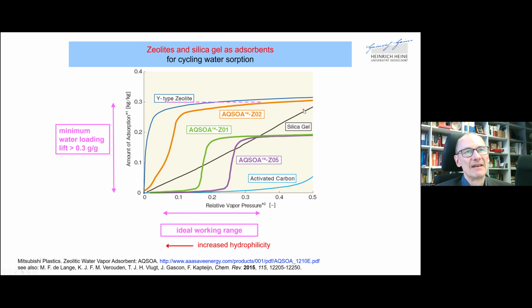So silica gel, because it's amorphous and has a quite large distribution of pores and pore sizes, will take up water over the whole range of water vapor pressure. And that is not really attractive, because if one works in this range here, there's only a small uptake over this range and not an S-shaped curve, which is advantageous, because you can work in a small window here and have the adsorption and desorption process by modifying the relative water vapor pressure.